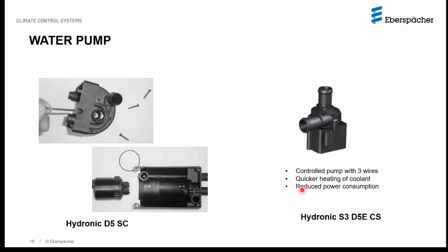The coolant pump itself, these are magnetic pumps. So if you have contamination in the coolant, of course, it will all get deposited in the pump itself, causing it to slow down. If your pump slows down, then of course the flow of coolant running through the heater is affected, and that basically will cause overheating issues, the heater switching off very quickly, etc.